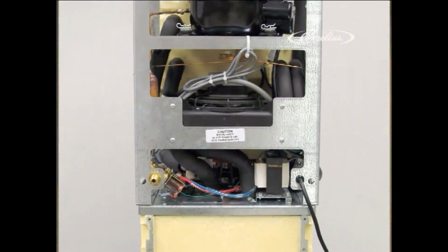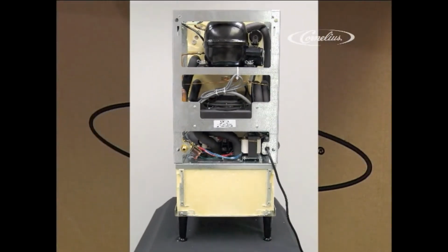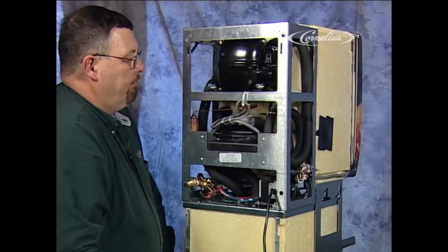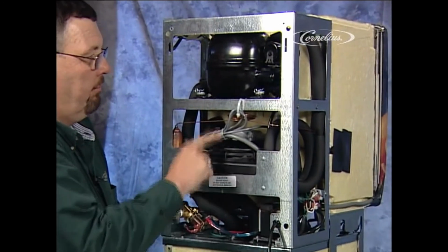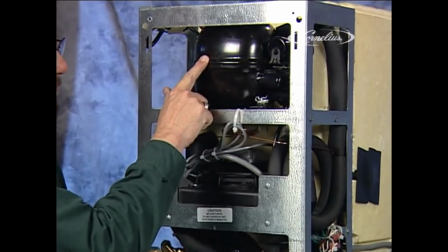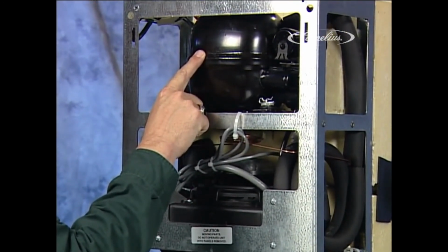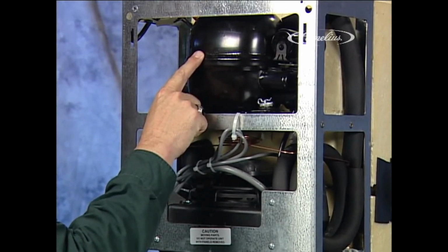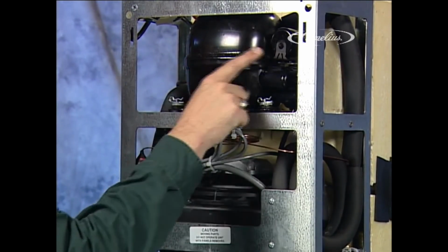At the same time, we have also checked that the relay is disconnecting properly. If during our system validation test the condenser fan runs but the compressor does not, we will have to use our voltmeter to run some checks on the compressor and its key components. Start with the start capacitor.